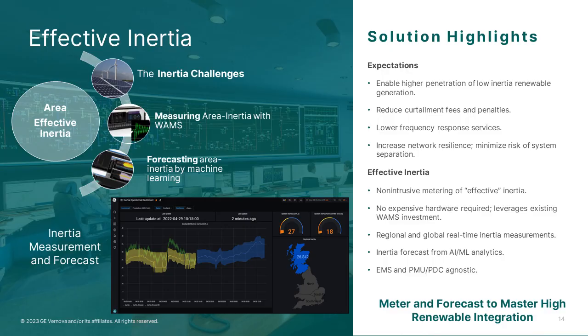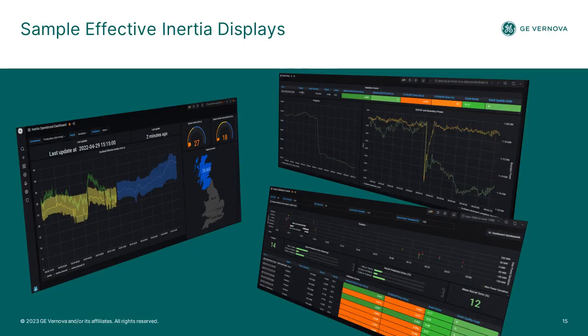We're taking that one step further. We are also able to forecast the inertia over the next 24 hours. Here, we use the WAMS data, but we also use the renewables forecast, the load forecast, and the conventional generation forecast, and translate that using AI/ML into an inertia forecast for the next 24 hours. That way, utilities can plan their dispatch and ensure that they maintain a certain amount of inertia on the system for stability reasons. Here are some examples of the displays that we have for effective inertia: trends of the inertia, the forecasting of the inertia, and we can also look at past events on the system to validate the inertia using data from those events as well.